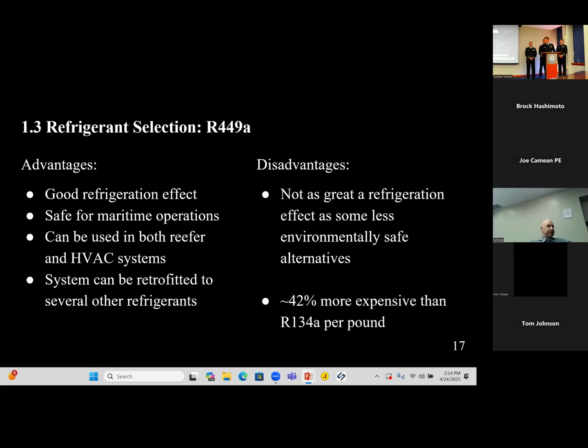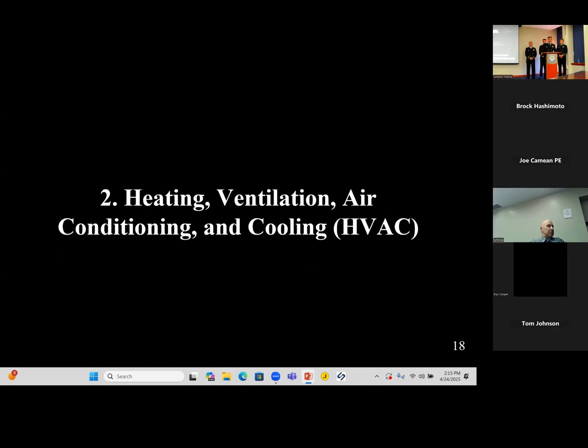It does have some disadvantages. It is not as great a refrigerant effect as some of the other alternatives. And it's about 42% more expensive per pound than R134A. So you may ask, is that 42% worth it? Well, consider that if this refrigerant gets phased out, you can easily swap the system without swapping the entire system simply by changing a couple components. Whereas R134A, the pressures that it operates at, it's likely you're going to have to change a lot more of the components. So the next thing we're going to talk about is the HVAC system.